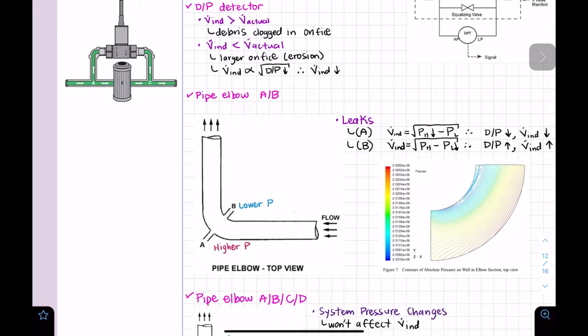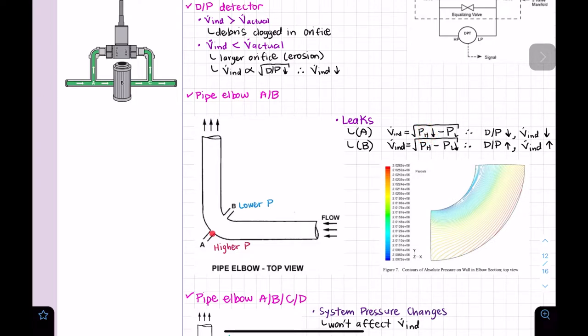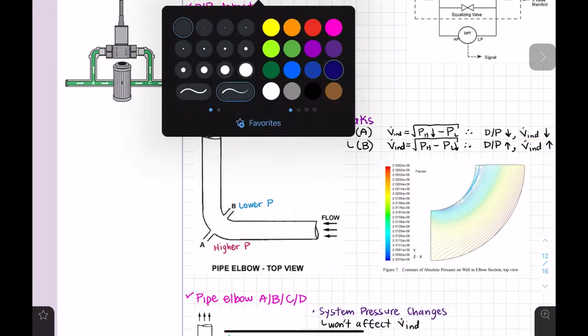If we have a leak on the high-pressure side of the elbow, we're reducing pressure in the high-pressure area. Using example numbers — if initially high is 10 and low is 5, giving a differential pressure of 5 — and we reduce the high side to 9, the differential pressure drops to 4. Reducing the differential pressure means the indicated flow will read low.